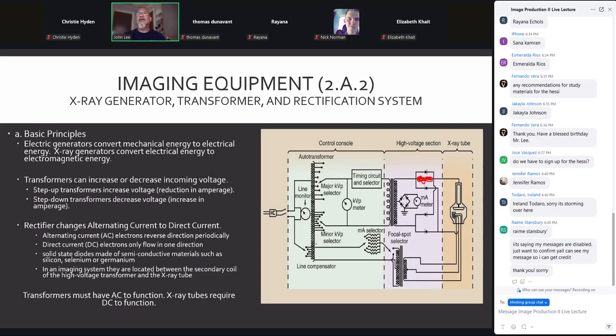Give me my pencil. Looking at our filament circuit, which is all of this, it goes up to the filament and includes all of this down here. Now, on the secondary side of that auto transformer, we're only using this many coils compared to our primary side, which is all of these. More coils on the primary side versus fewer coils on the secondary side means step down. So the voltage coming in, be it 110, 220, 440, whatever, when it comes through here, depending on the transformer ratio, the voltage is going to decrease.